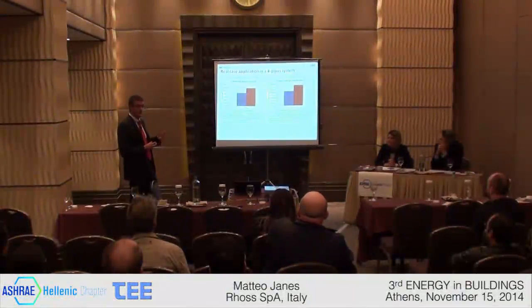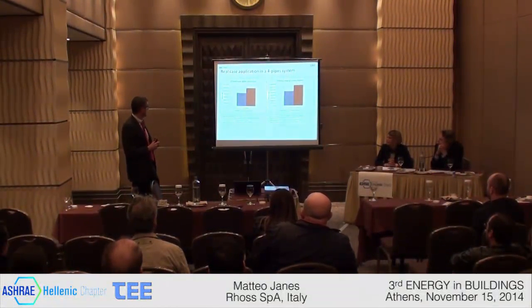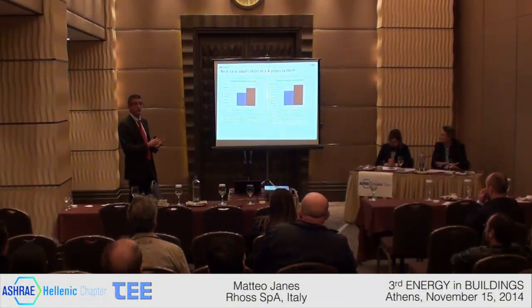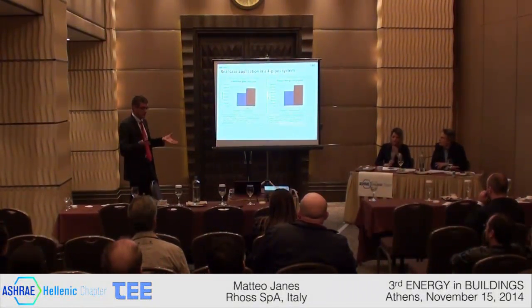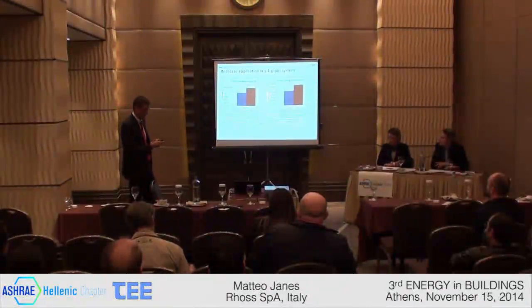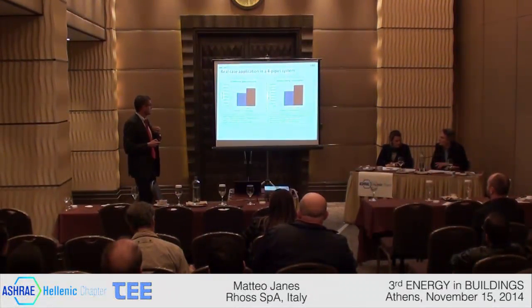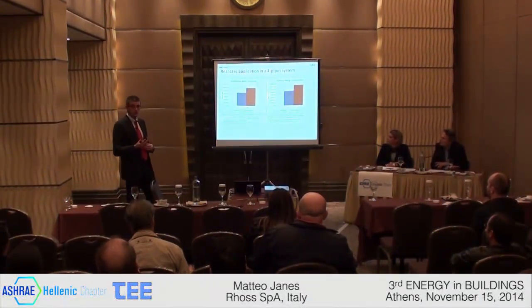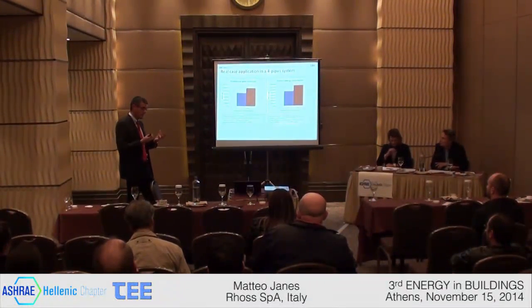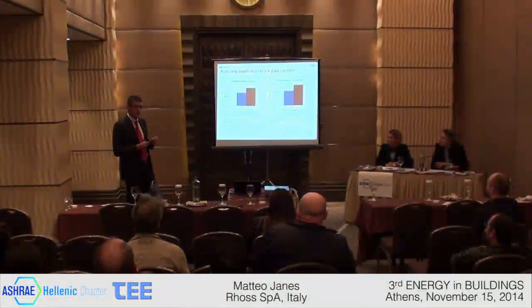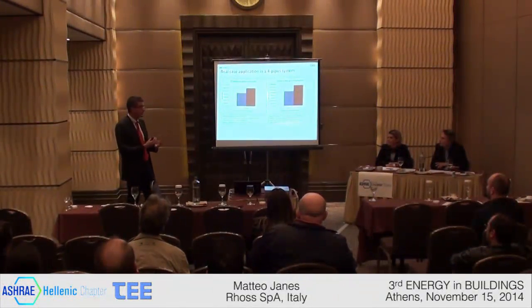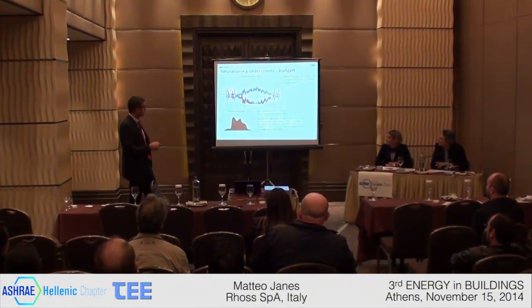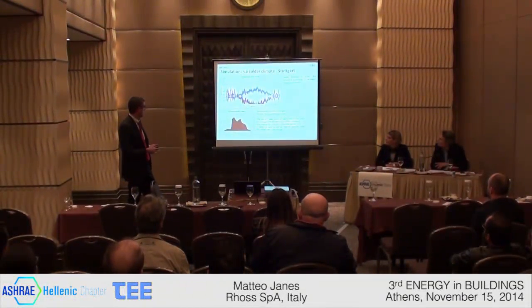The building was occupied, as I mentioned, at the end of 2011, and the energy consumption is monitored all year round because the building is controlled by a BMS system, and the real data show consistency with the analysis that we have done. But in order to understand if this technology could be applied even in a much colder city, so in a much colder climate where the use of a heat pump during all year round is not economically convenient, we've made a simulation of a similar building with the same features, same size, same envelope, same glazing, but installed in a much colder city, which is Stuttgart in Germany.